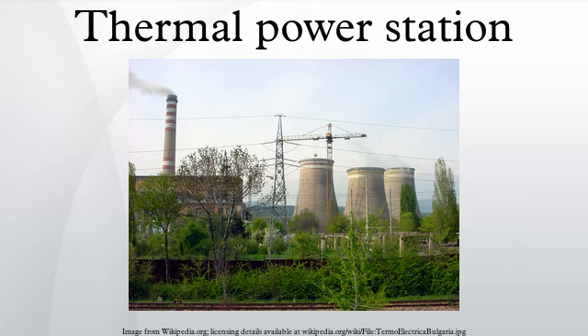Thus, the salts have to be removed from the water, and that is done by a water demineralizing treatment plant. A DM plant generally consists of cation, anion, and mixed bed exchangers. Any ions in the final water from this process consist essentially of hydrogen ions and hydroxide ions, which recombine to form pure water. Very pure DM water becomes highly corrosive once it absorbs oxygen from the atmosphere because of its very high affinity for oxygen.